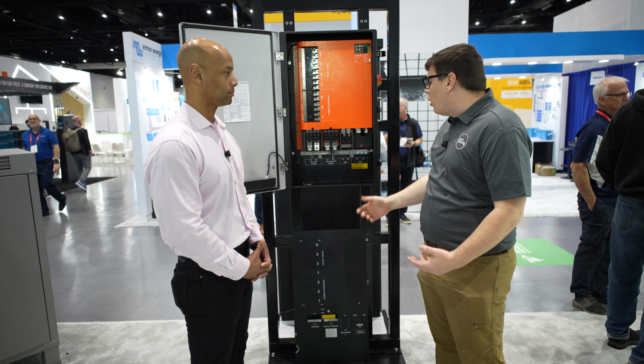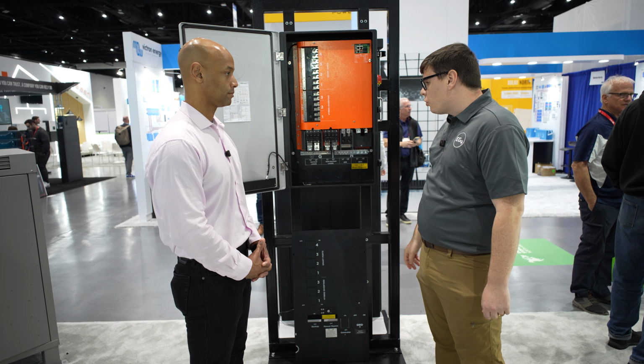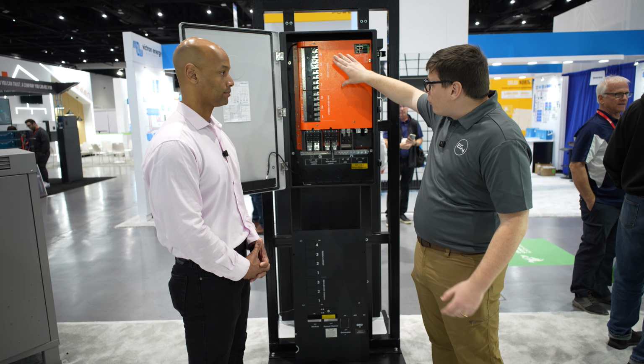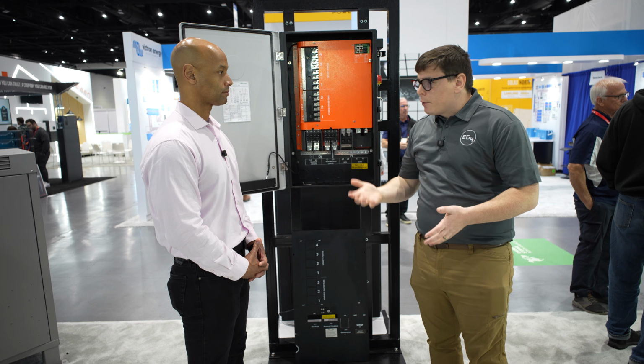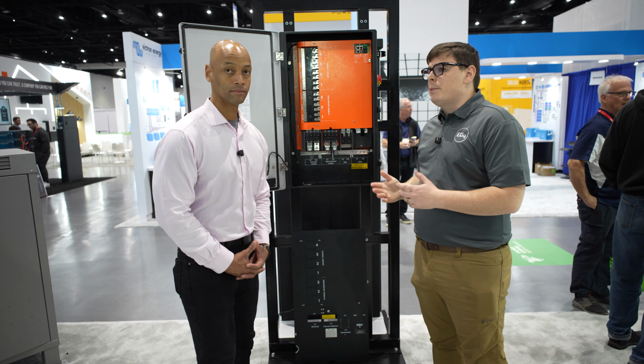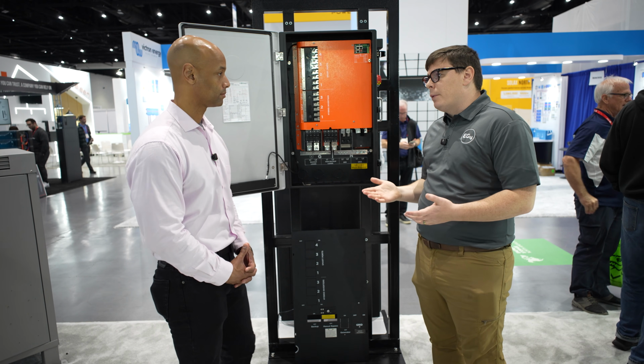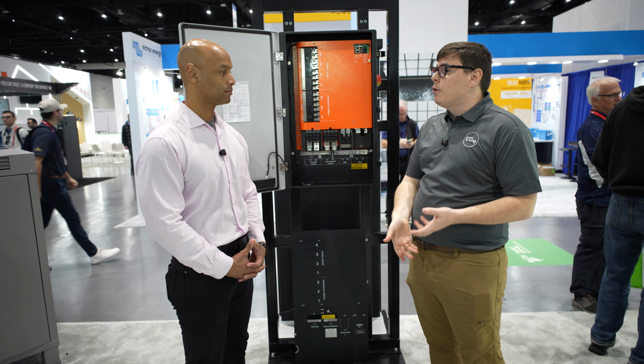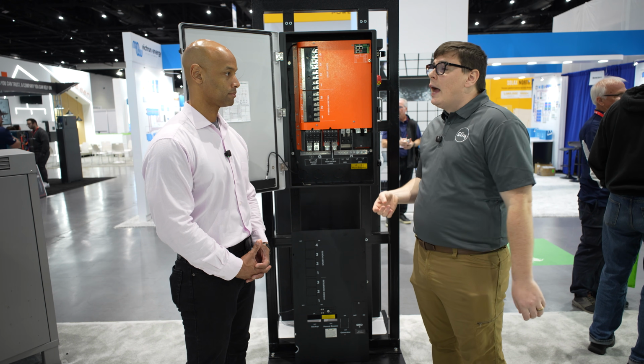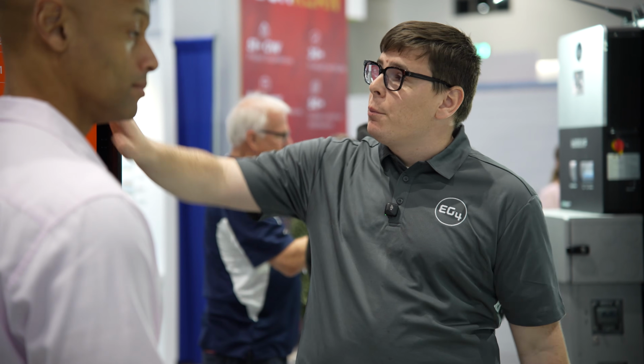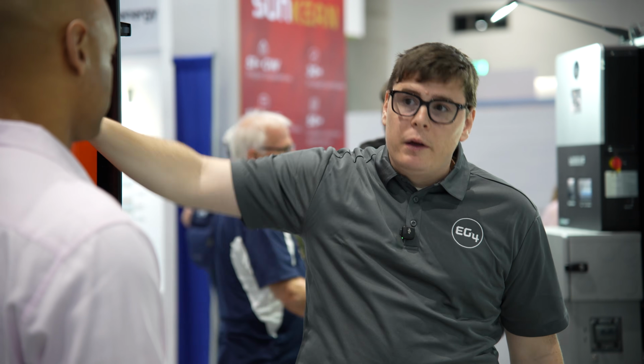So other than that, just think about the smart load ports—I can't stress this enough. If your company's selling backup, take the extra 30 minutes, get a load plan with the customer, or bring a clamp meter to the site and watch their energy usage, and pick the loads that are actually at risk and put them on the smart loads before you leave. That way, if there's a backup situation, they've got enough power to succeed, and you as an EPC can help the customer out without rolling a truck, handling it in an automatic way.